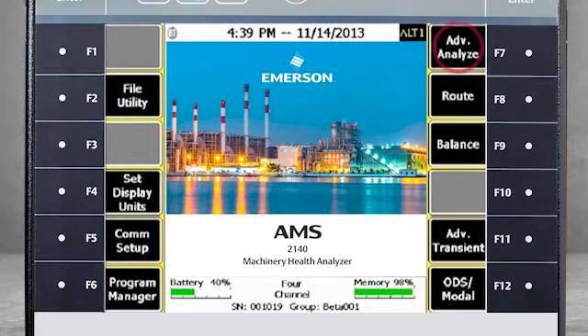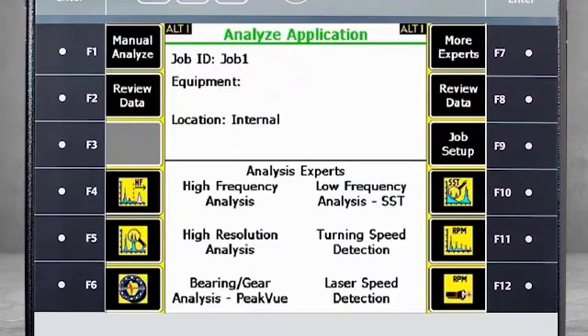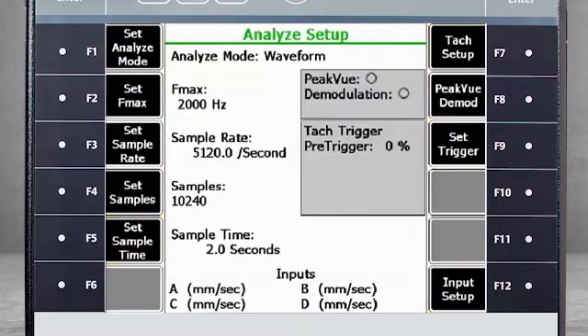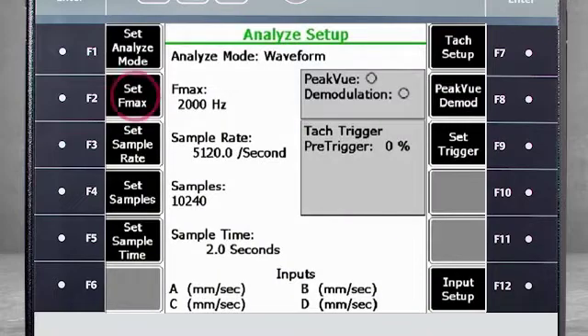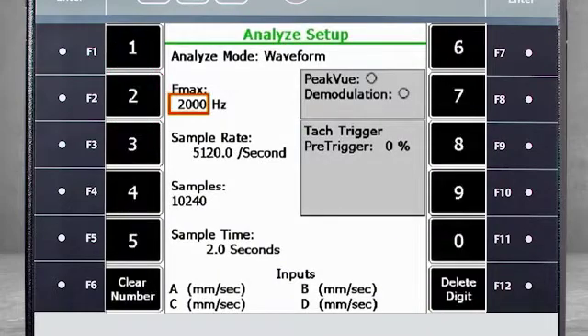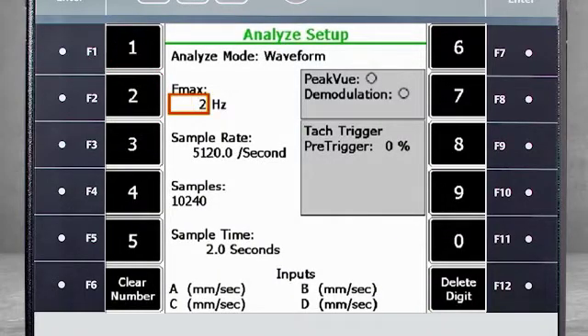Start by selecting F7 Advanced Analyze and then F1 Manual Analyze. Select F1 Set Analyze Mode and choose Waveform. Select F2 Set F Max to specify the maximum frequency. Here we will use 2000 Hz.